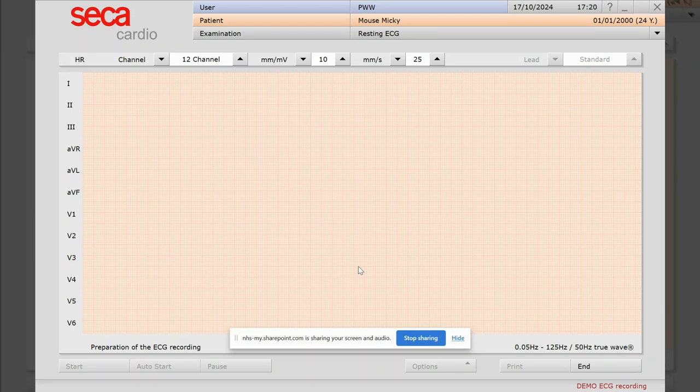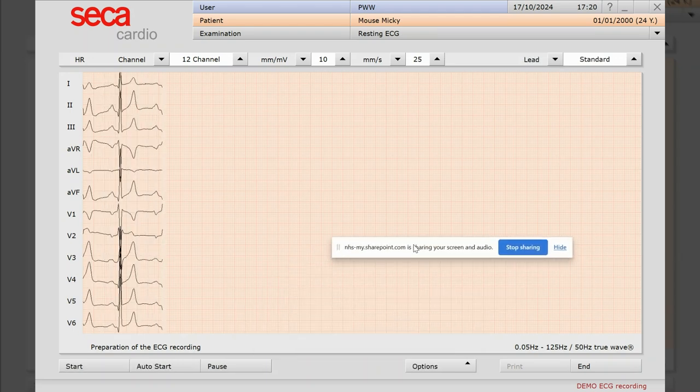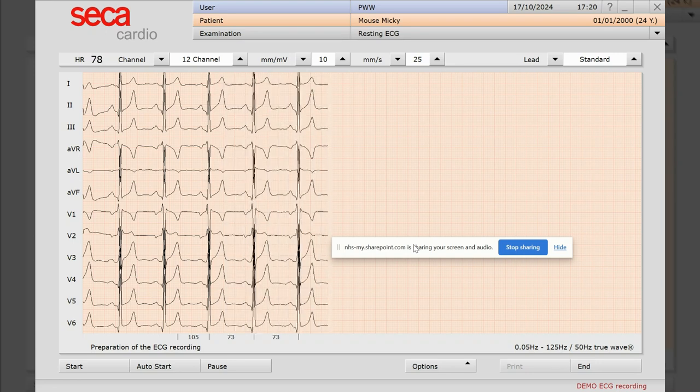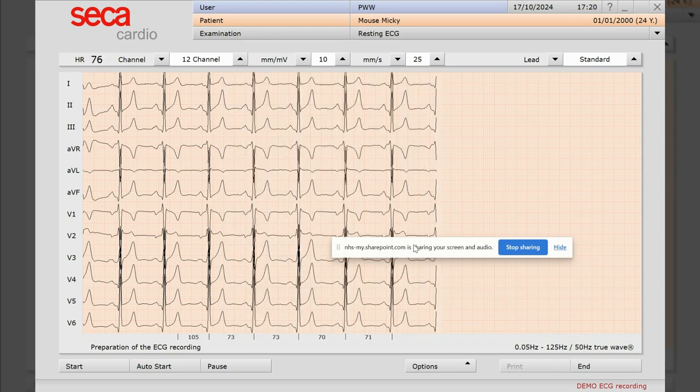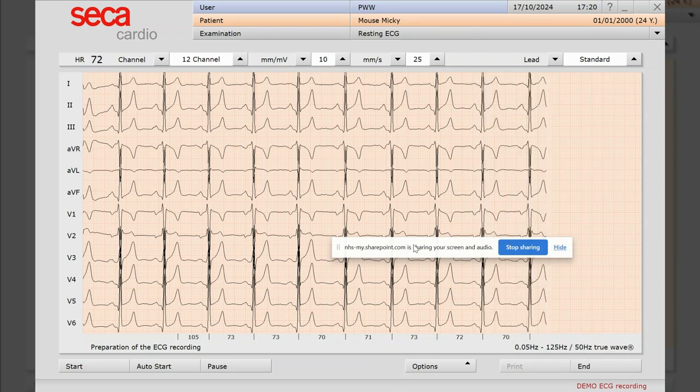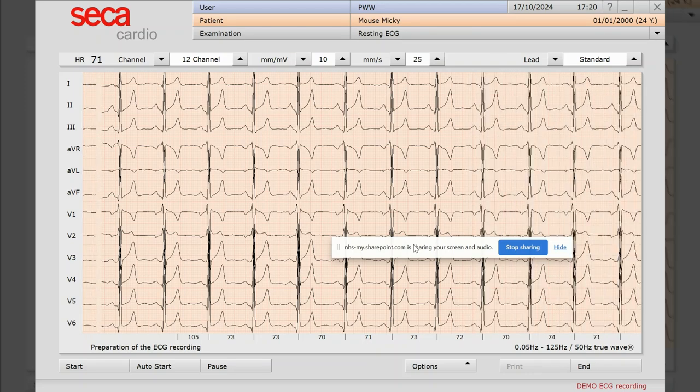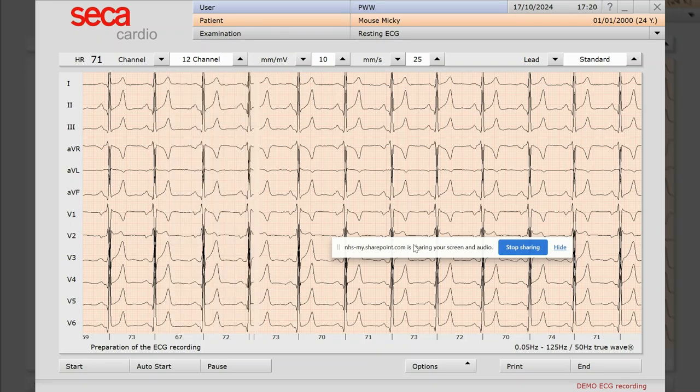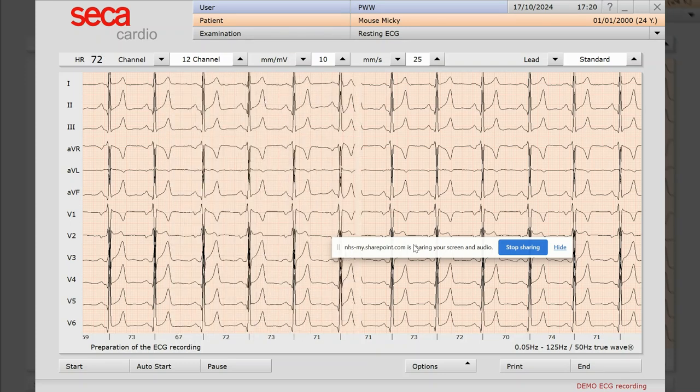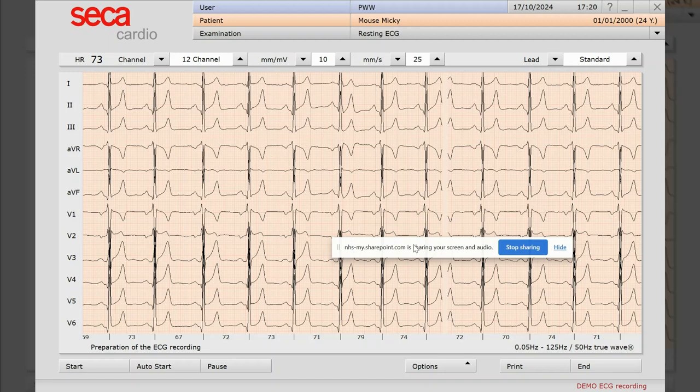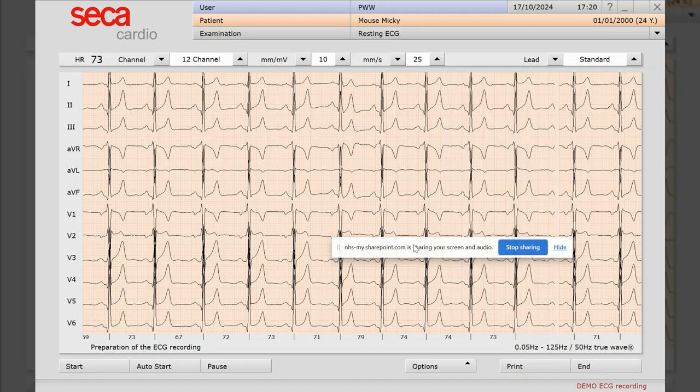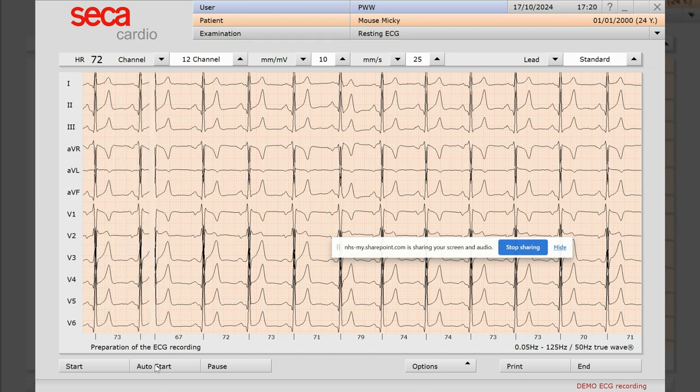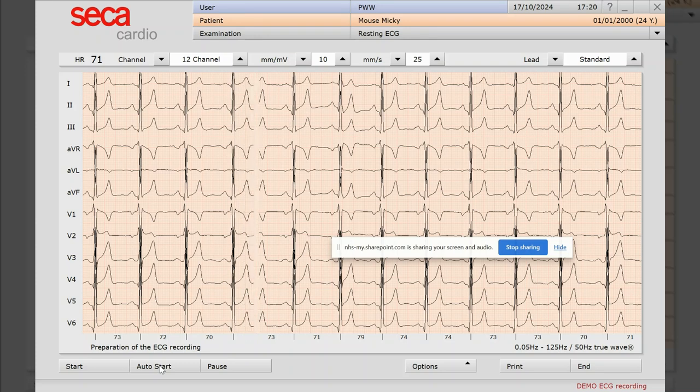And then what will happen is you'll get a screen appear and you'll start to see the ECG appear on the actual device itself. If you've got a green light next to one of the leads, it's happy. If you get a red light next to one of the leads, it means that lead doesn't have a good connection. But when you're happy on the screen that you've got a good quality ECG, either press the button on the device, the on button briefly, or you can press the auto start button.